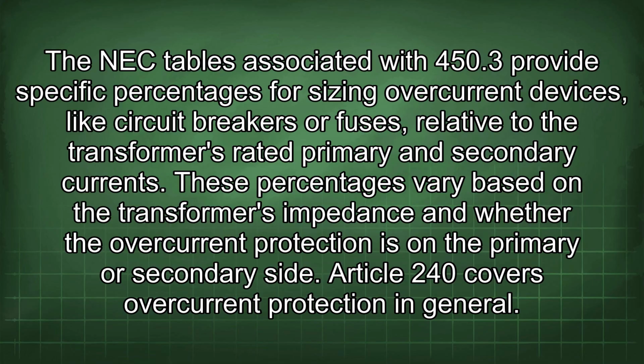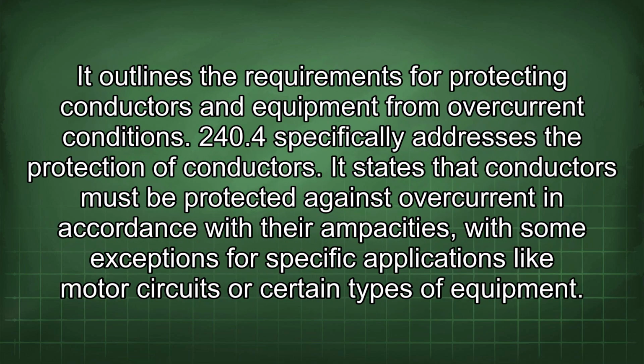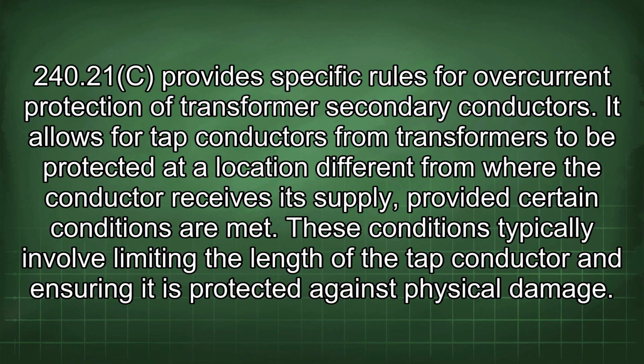Article 240 covers overcurrent protection in general. It outlines the requirements for protecting conductors and equipment from overcurrent conditions. 240.4 specifically addresses the protection of conductors. It states that conductors must be protected against overcurrent in accordance with their ampacities, with some exceptions for specific applications like motor circuits or certain types of equipment. 240.21c provides specific rules for overcurrent protection of transformer secondary conductors. It allows for tap conductors from transformers to be protected at a location different from where the conductor receives its supply, provided certain conditions are met. These conditions typically involve limiting the length of the tap conductor and ensuring it is protected against physical damage.